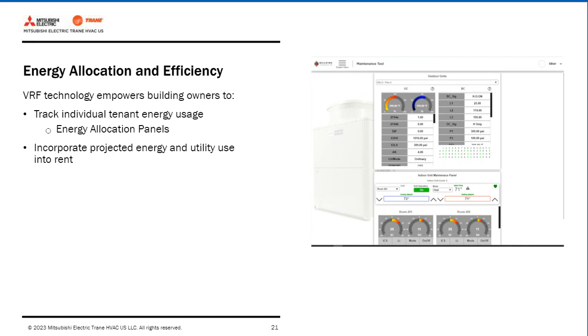And in spaces where you need to do tenant billing, that's another option that VRF makes it easy to do. The inverter compressors only use the exact amount of energy needed to reach a zone set point. That said, it's a huge benefit for all types of buildings with tenants. If a building owner bills individual tenants for energy consumption or needs to bill for excessive usage, energy allocation controls can be applied to VRF systems, which are a huge advantage. This solves the challenge of energy consumption billing for multiple tenants.